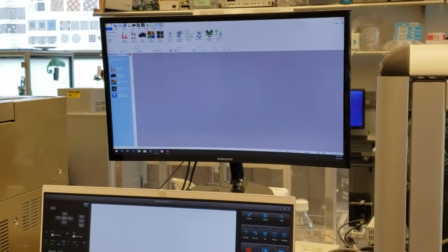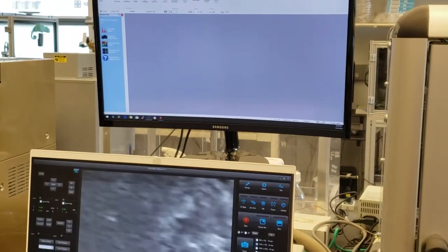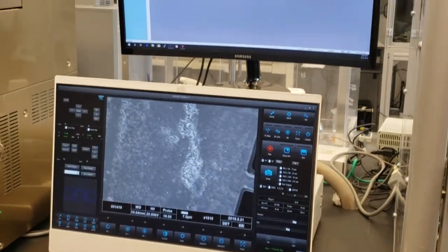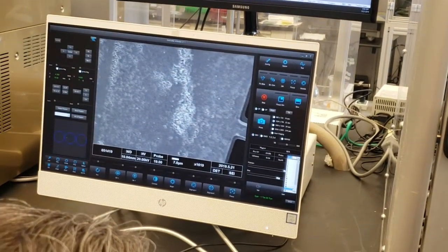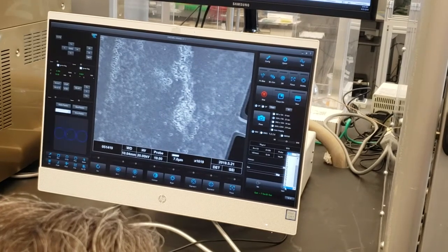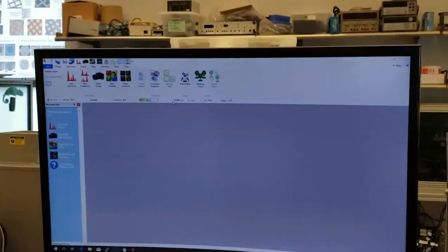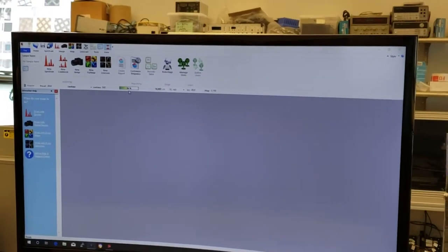But you want that ratio to always be somewhere acceptable, for instance in the green of the traffic light, or green to yellow. So if I open this up even more, let's go full open to 20. Now I've got 16,000 counts a second, and I've got 37% dead time.